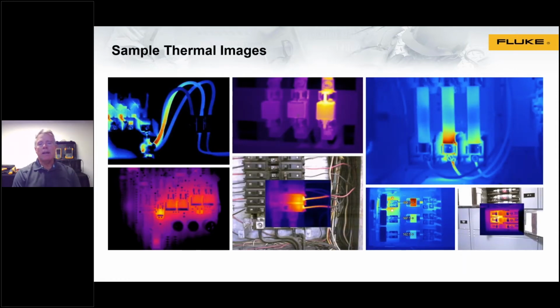I have a few sample thermal images here, and again, I'm sure that many of you have seen examples of that, but there's a few examples that we show here. Namely, what you're looking for are evidence of potential problems. This might be an example of a loose connection where you see a hot spot and then moving on the conductor up away from that hot spot, it appears to get cooler.